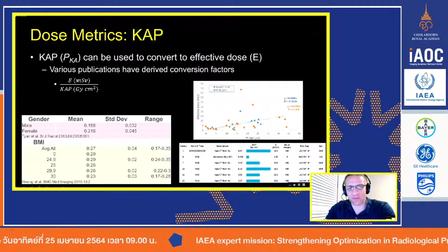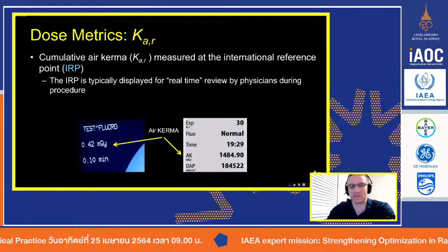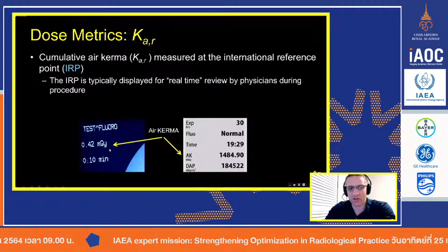Excuse me. The next dose metric that's very important is the cumulative air kerma. And the R in the subscript stands for at the international reference point, which I'll demonstrate in a second. So the cumulative air kerma at the international reference point is a value that will always be, especially on the newer scanners, older scanners, not so much, but basically for the last 10 to 15 years, it's been required by all vendors to show this value on the screen.